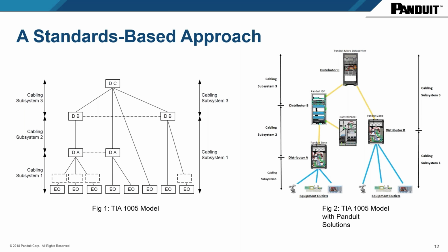As you come down to the next layer in the star topology, where now you are on the factory floor systems, you're talking about distribution Bs and so forth. Those types of distribution frames and zone enclosures are the type of systems where inside each one of those enclosures, you may encounter commercial grade product, but connectivity on the outside and between these devices has to follow the MICE norms.